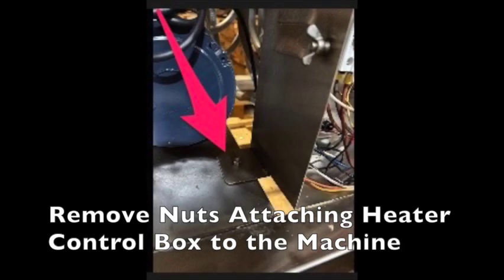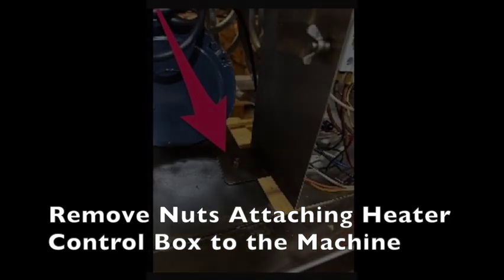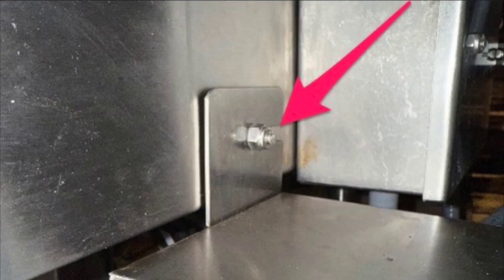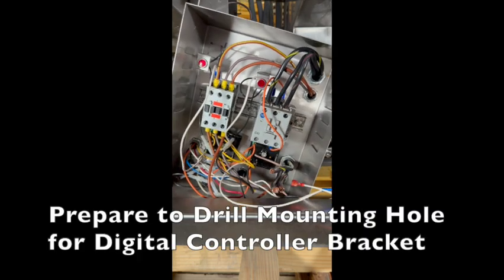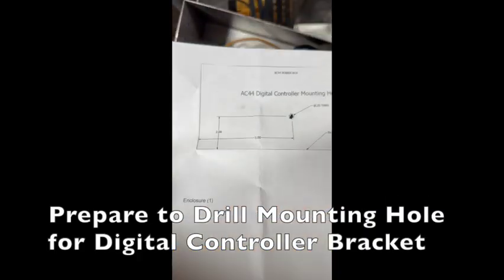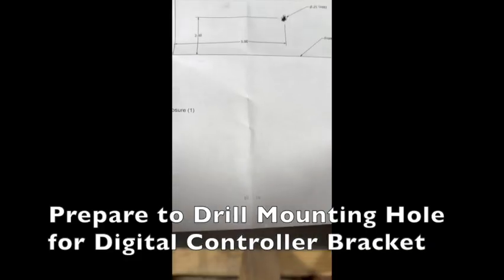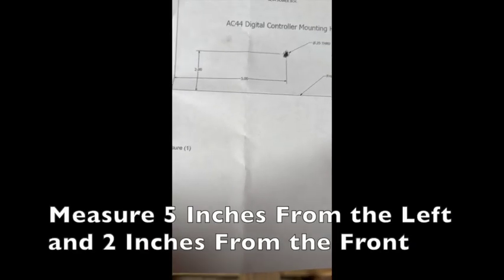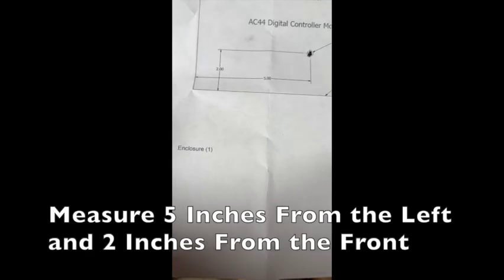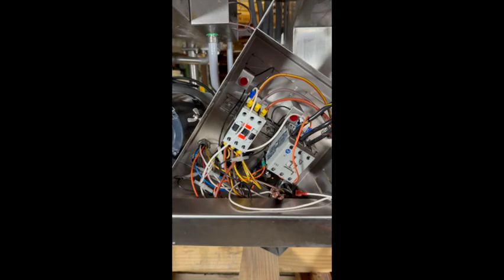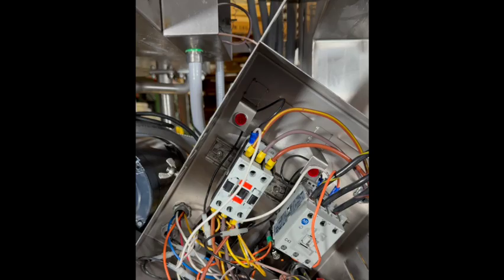actually installing the digital controller to the heater control box. So we do have to drill a mounting hole for it. You do have a template included in the kit. You've got to remove that control box from the machine. There are two 7/16 nuts that hold that control box to the machine.